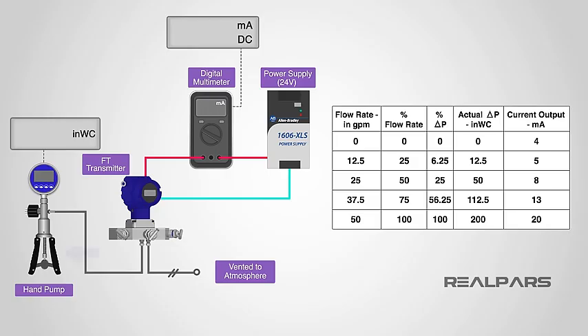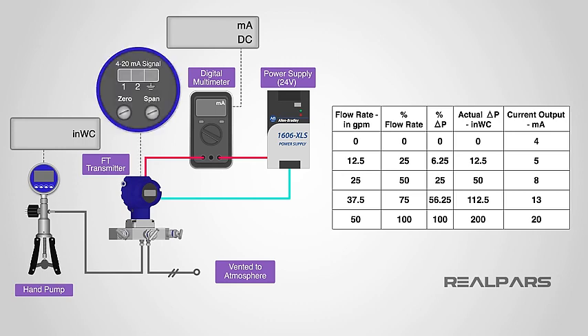We begin by applying the desired pressure input values from the calibration table to the high input on the flow transmitter and record the output current measured for each input value. If the output currents measured are outside of the acceptable ranges as established by your company, then the transmitter must be recalibrated using the zero and span adjustments. We perform the actual calibration using the zero and span adjustments on the transmitter.